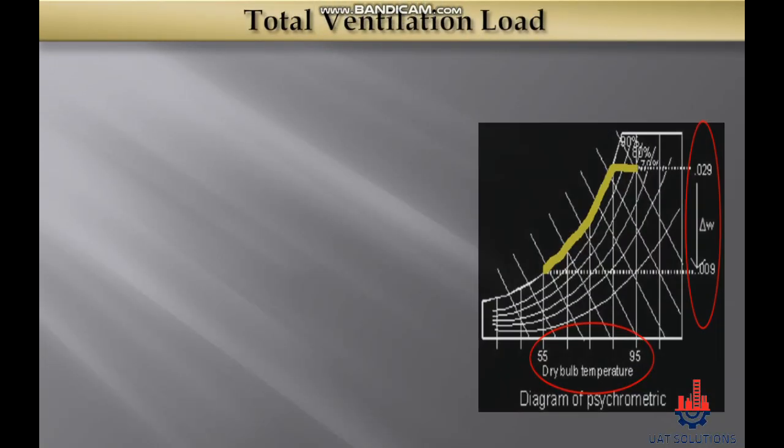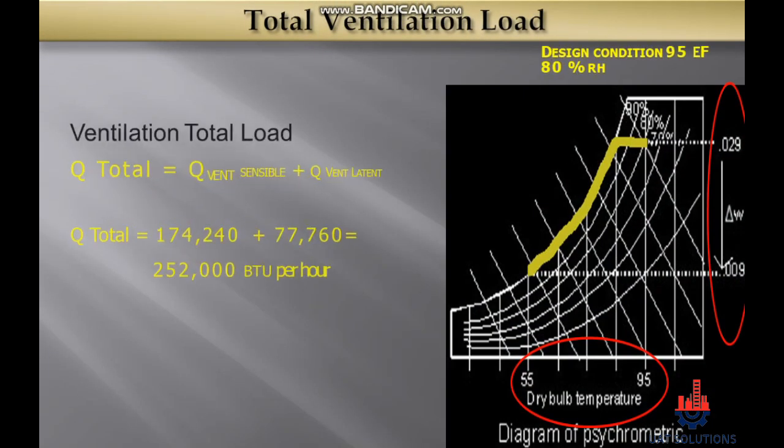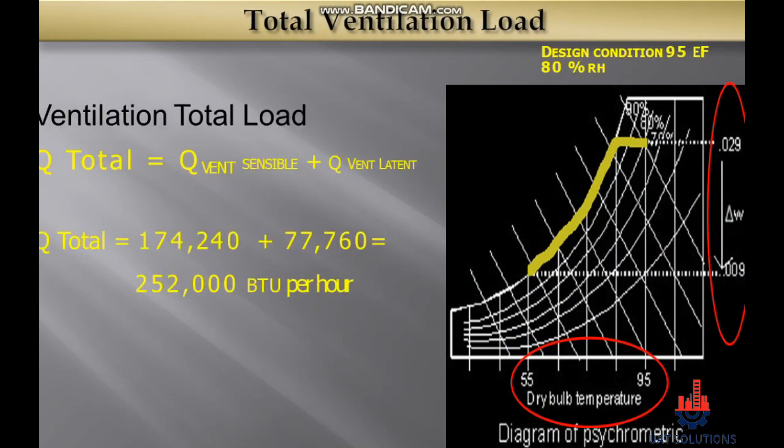Now that we have calculated and converted ventilation sensible and latent cooling load, let's combine them: 174,240 plus 77,760 equals a total of 252,000 BTU per hour.